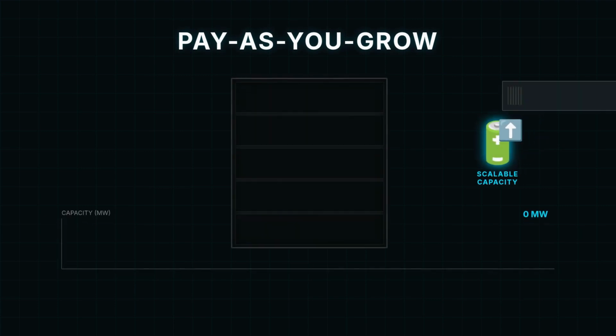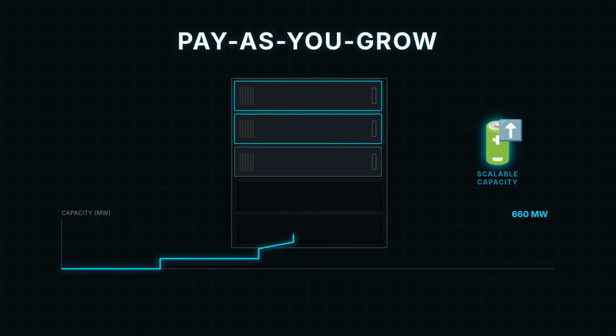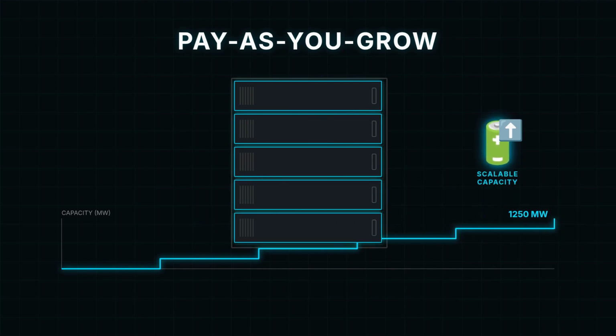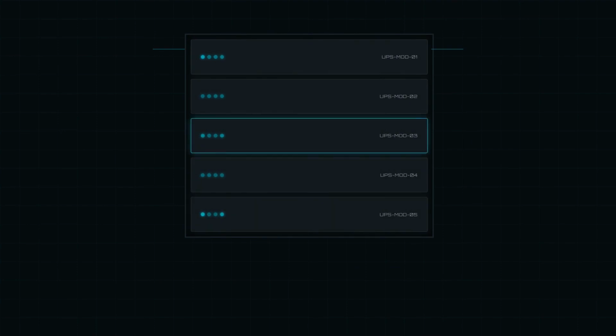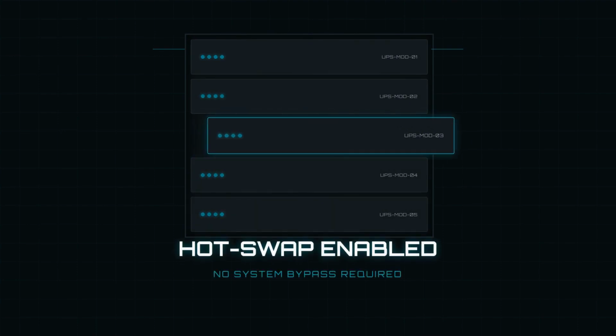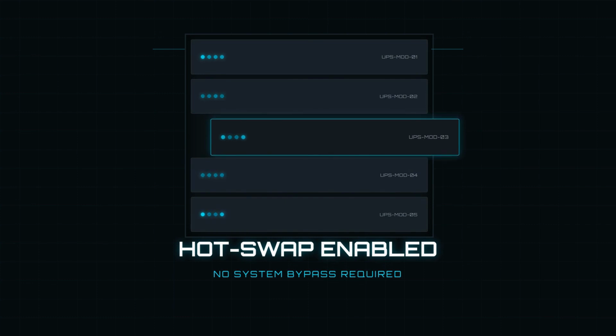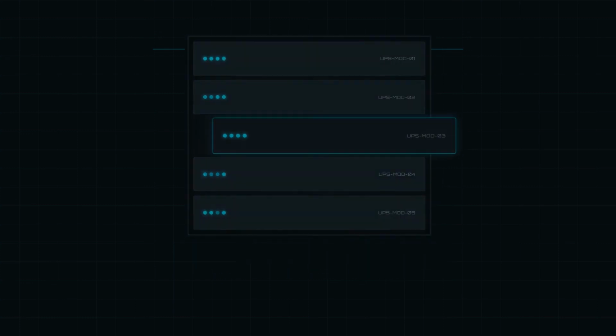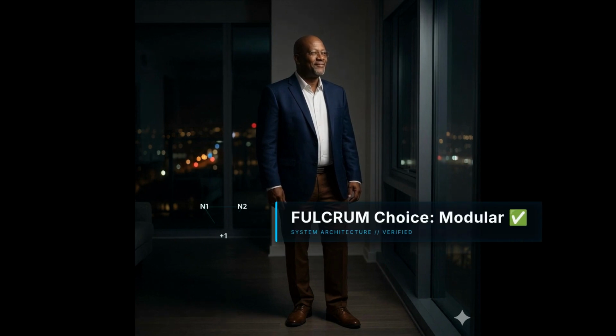Scalability is a massive commercial and technical advantage. Instead of being locked into a fixed capacity from day one, we can add modules to existing frames as the IT load increases. This is the pay-as-you-grow engineering model that fits hyperscale growth. Maintenance is transformed. Instead of requiring a full system bypass for internal work, we can hot swap individual modules while the UPS continues to protect the load. This eliminates a significant single point of failure and keeps our uptime at 100%. For a project like FULCRUM, modular is the only logical choice. The combination of scalability and hot swap capabilities is critical when managing critical backup power at an 85 megawatt scale. It is about future-proofing the machine.